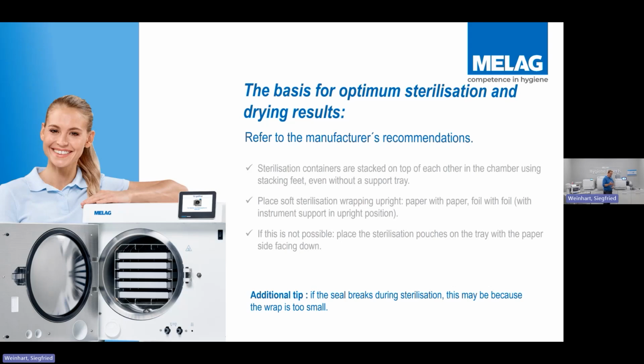Likewise with pouches, it's important that you don't overload the actual tray. You wouldn't want any more than a third of a pouch cropping onto the next pouch, because obviously what happens then is you inhibit any drying capability. So you certainly wouldn't want a pouch on top of a pouch. You could put a pouch next to that, but if the pouch next to it is slightly too big, you'd be looking at no more than a third coming onto this pouch. Okay? Otherwise you inhibit the ability to dry the pouches correctly.